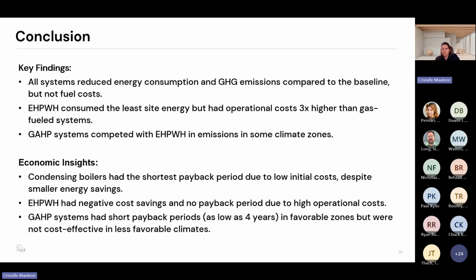The GAHP systems performed well in terms of emissions, especially in cooler climate zones, and in some cases matched or outperformed the electric heat pump water heater. Economically, the condensing boiler had the shortest payback period thanks to its low upfront cost, even though its energy savings were modest. The electric heat pump water heater didn't have a simple payback due to its high operating costs.